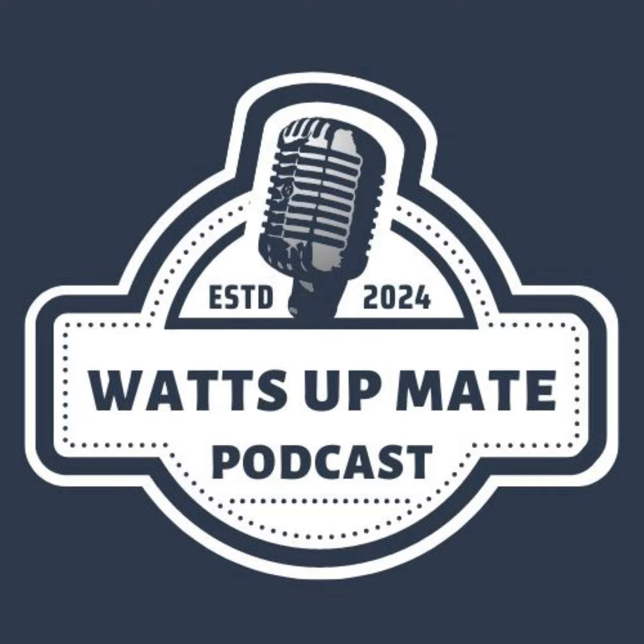Funny, talking about switching neutrals, sometimes it's actually a requirement for some appliances, especially things like gas cooking appliances or heating appliances. A lot of contractors do this by providing a plug and socket, so gas service techs can actually unplug the equipment fully. Others use double pole or multi-pole isolation switches or isolators for this purpose. We use both methods depending on accessibility generally, and also the requirements for isolation of the equipment, usually mentioned in the installation manual or the gas regulations.